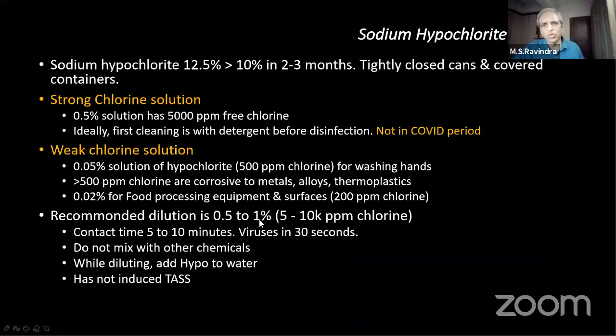1% is too harmful, too toxic. It gives off too much chlorine outside. For ophthalmic work, where we're not dealing with COVID directly, though presumably we treat chlorine, 0.5% is adequate. 10% diluted 20 times is 0.5%. It's got 5,000 ppm. Even this is very strong. In food, they use 0.02. This is 20 times more diluted than that. So it depends upon the instrument. What we use is 0.5%.